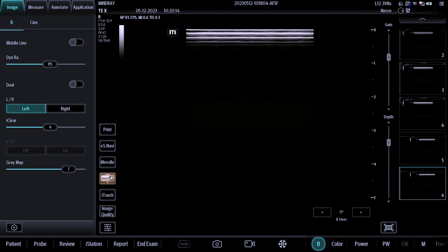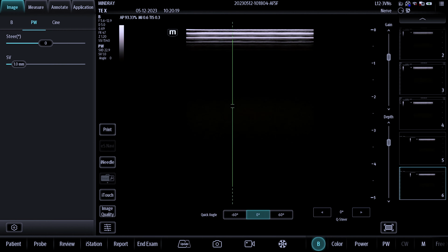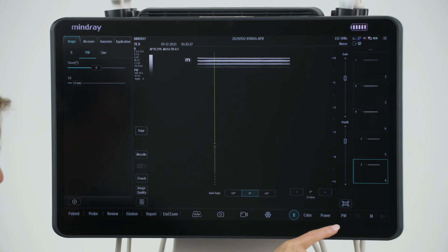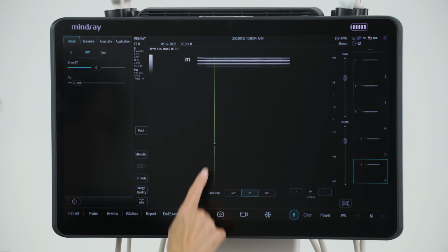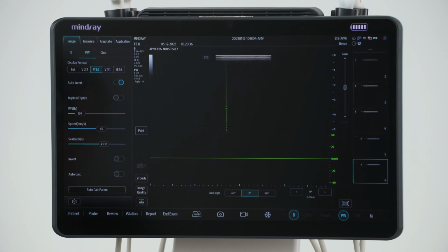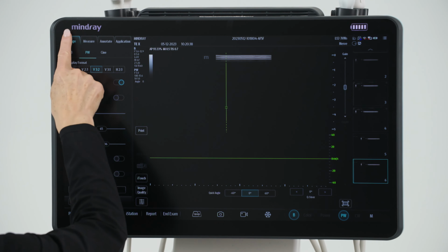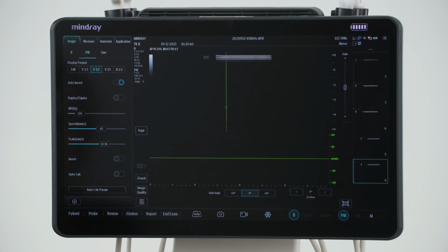To enter pulse wave Doppler, press the PW key. Position the PW sample gate in the desired position with a finger. There are three ways to activate Doppler. Press the PW key again, press the update icon, which is lit in white, or double tap on the PW cursor. Notice while in PW mode, the options under the Image tab have changed to PW, which is highlighted blue.